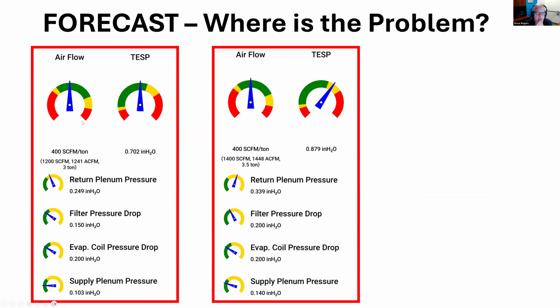This will break down the system into components, just like we saw before in the measure in process. The filter pressure drop and the evaporator coil pressure drop, those are just the numbers that I gave it because I looked them up from the manufacturer's literature. But the return plenum pressure and the supply plenum pressure, those are predicted for the 1200 CFM that's required for the 3 ton or 1400 CFM that's required for the 3.5 ton.